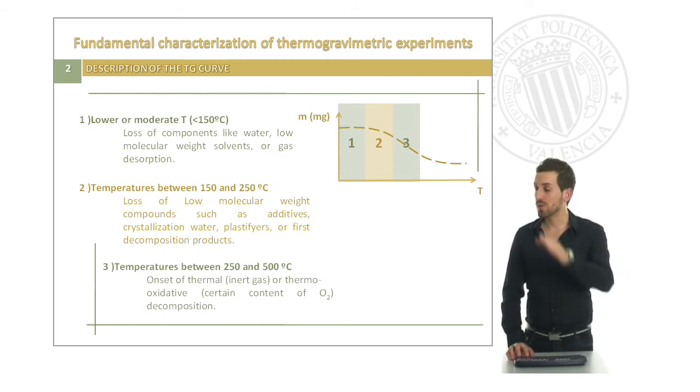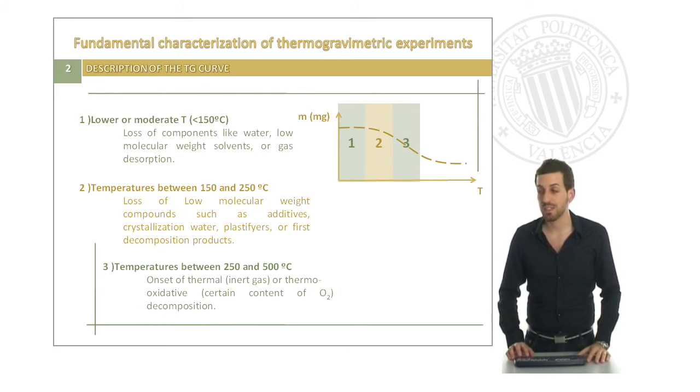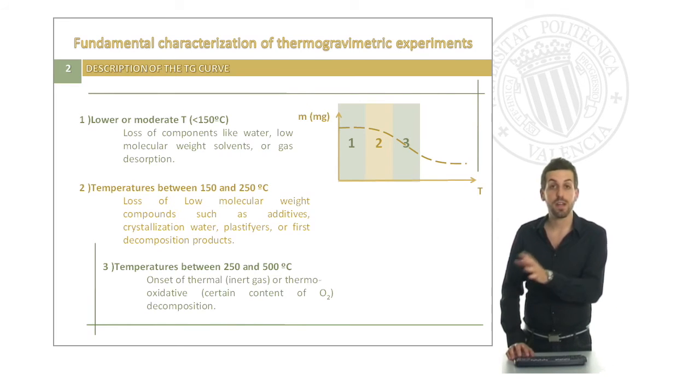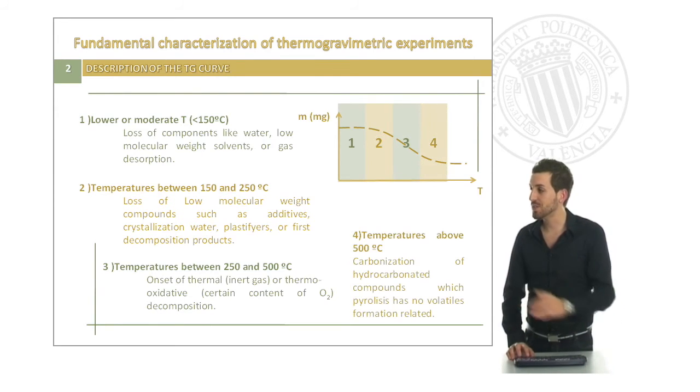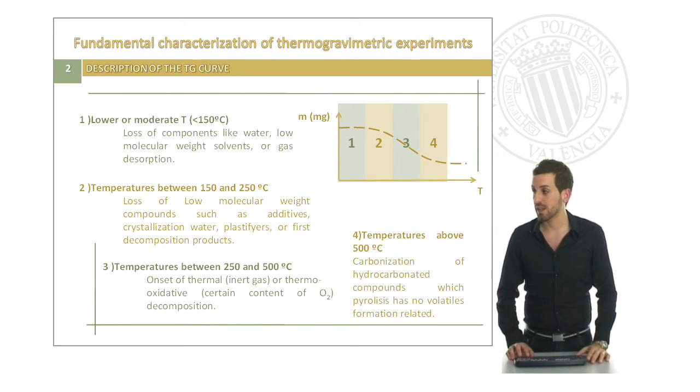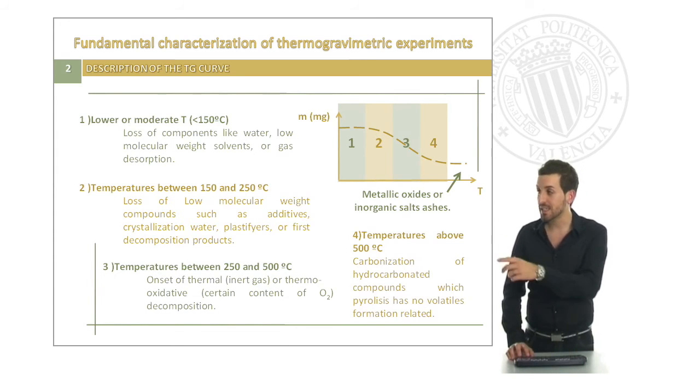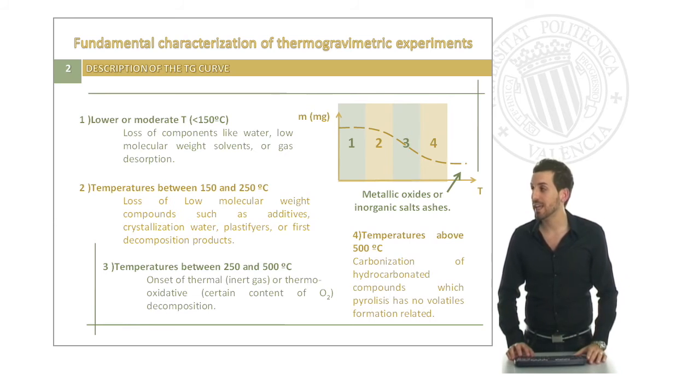When we go to the change of slope in temperatures between 250 and 500 Celsius degrees, we will be able to see the onset of the thermal, if we are analyzing in inert gas, or the thermo-oxidative, if we allow certain content of oxygen composition. If we increase the temperature above 500 degrees, we will find some processes such as carbonization of hydrocarbonated compounds, which pyrolysis has no volatile formation related. At the end, we will see the presence, or not, of some different metallic oxides or inorganic salts ashes.